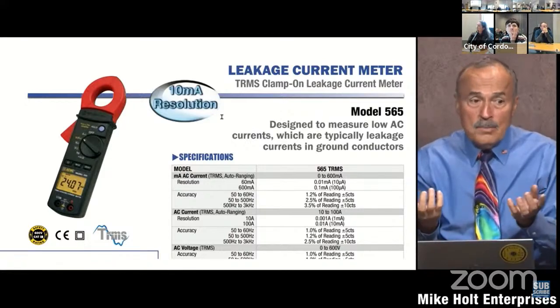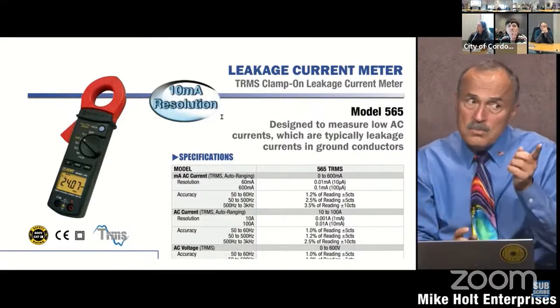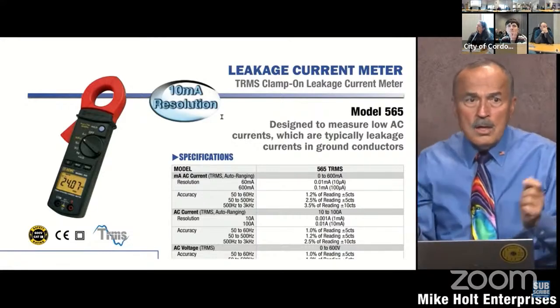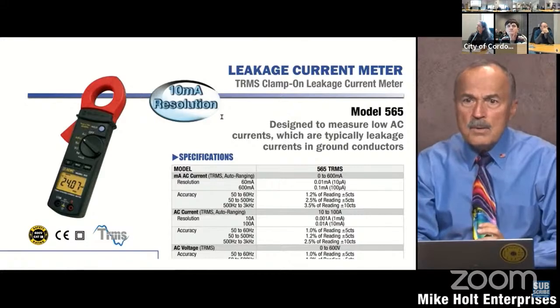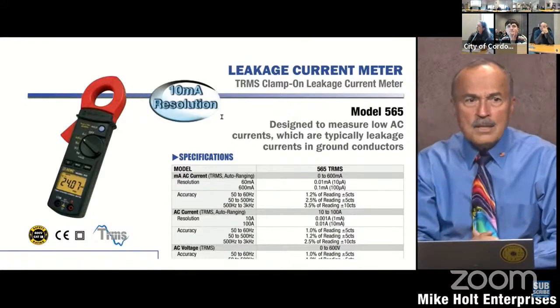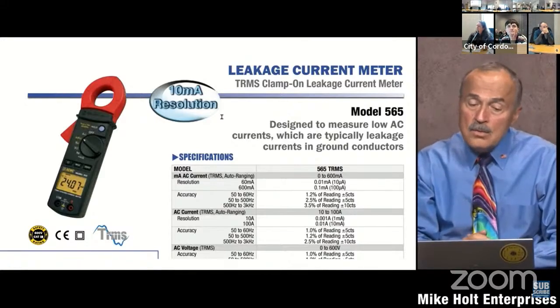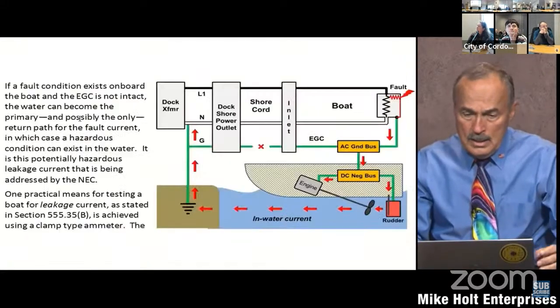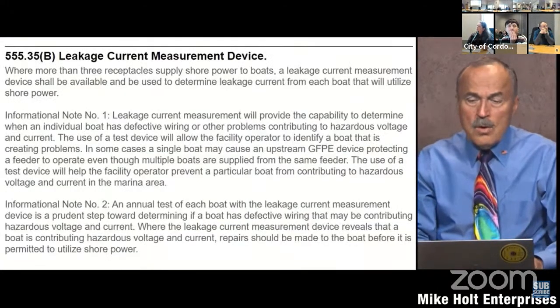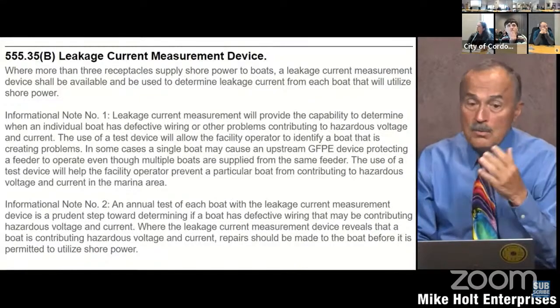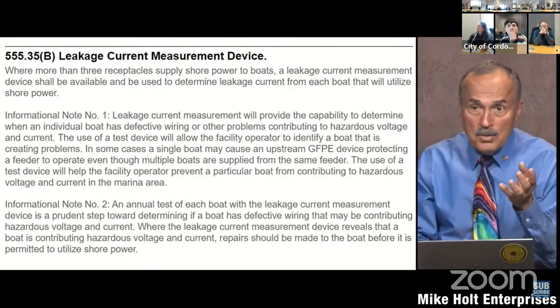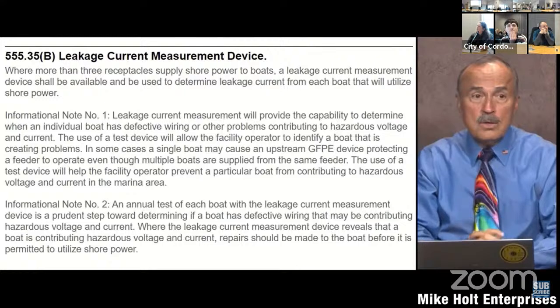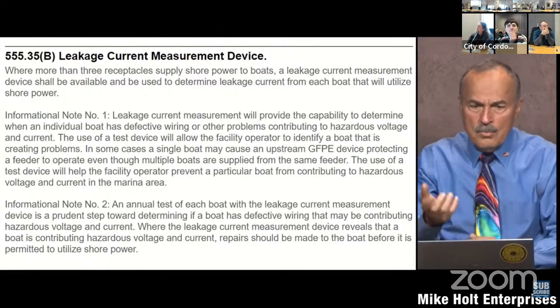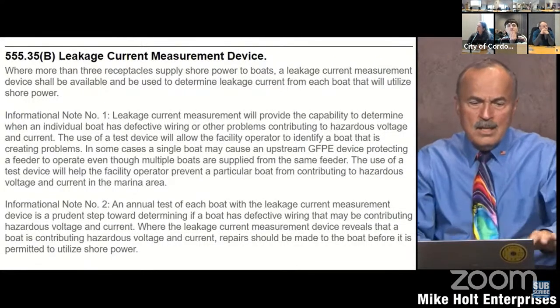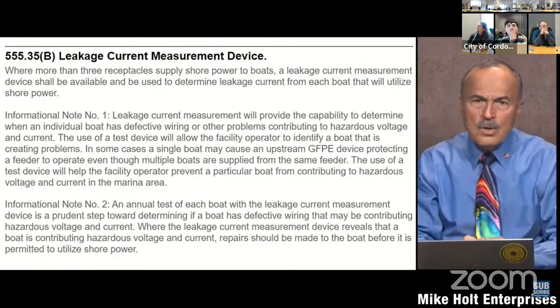Not only that, but if you did determine, well, this one is 27 and this one is 18, well, then we want to move you all. Are you actually going to be moving these boats all over the place because they're all operating within 30 milliamperes? And so there's a problem to me, in that the code is requiring a leakage measurement detector. It really won't matter, because if it's tripping because it's more than 30 milliamperes, I already know which one's the one that's over. Right. And why are you requiring somebody to have a tool? And then it goes on to the informational note about what it's trying to do.